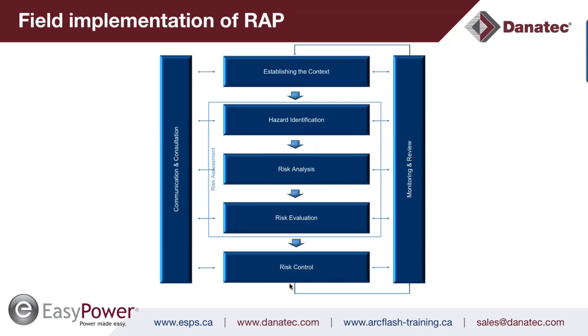The high-level flow chart for risk assessment involves: establish context, identify hazards, perform risk analysis and evaluation, apply risk controls, and then monitor and review those controls — which is the field documentation component. There must also be communication and consultation with workers who will be exposed. If a committee does the risk assessment, there must be communication and collaboration with the greater community of electrical workers and contractors. If you only use contractors, you must work with them to communicate the hazards, assessed risks, and residual risk levels if the hierarchy of controls is applied.